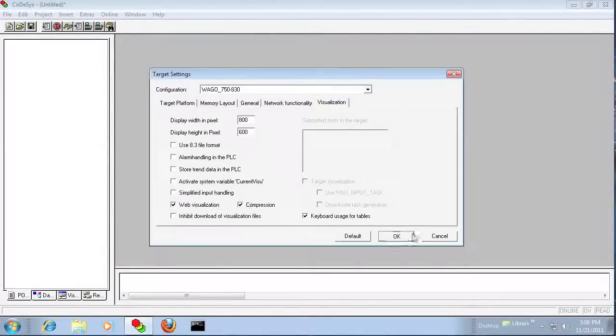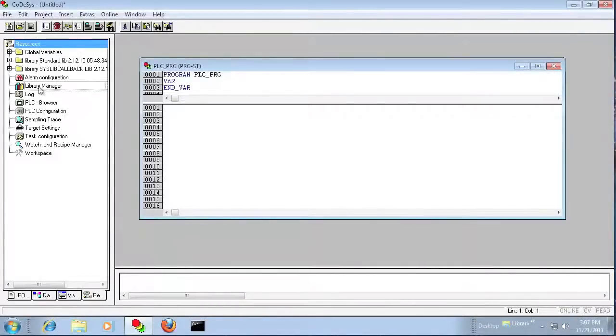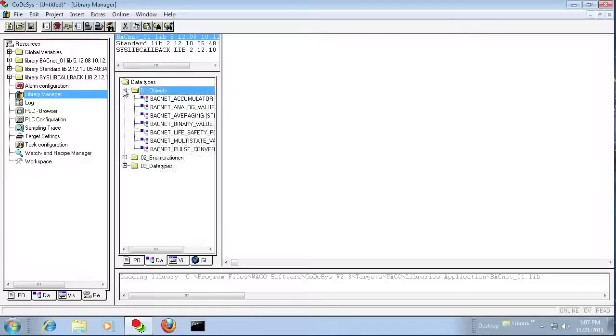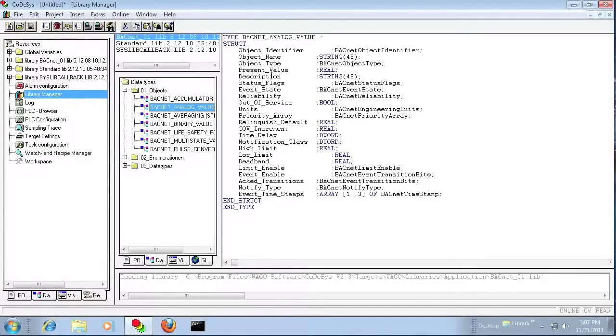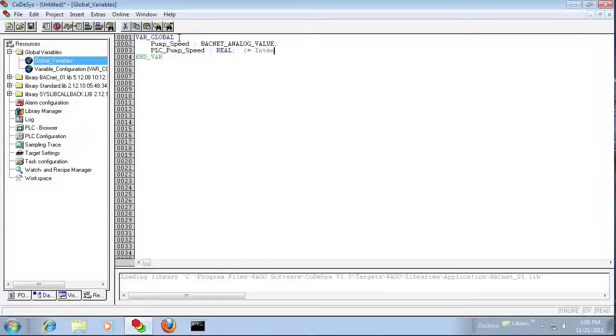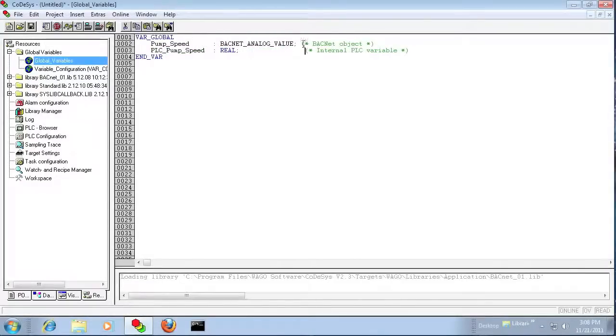Starting the Codesys project, I'm going to program this in structured text. I'll add the BACnet library, which gives you pre-made objects that populate the BACnet network with present value and units. I'm going to copy the BACnet analog value type and create an object called pump_speed, then create an internal real variable called plc_pump_speed. This is a simple example with just one variable, but you could populate dozens — up to 1,000 BACnet objects if needed.